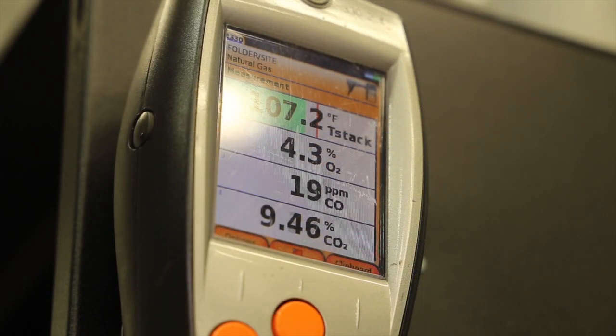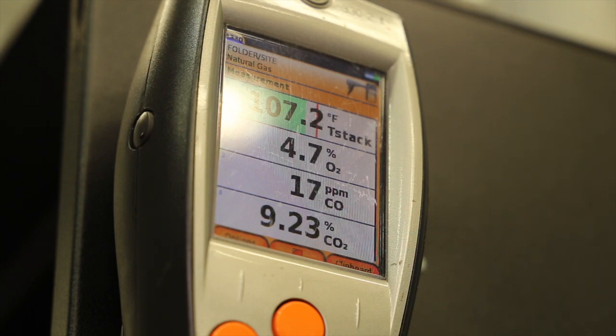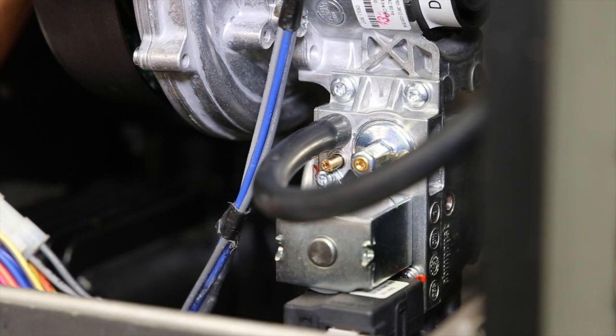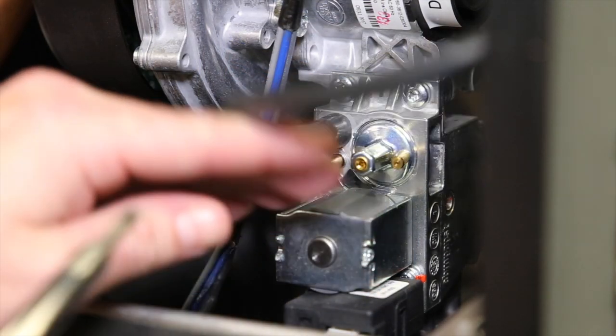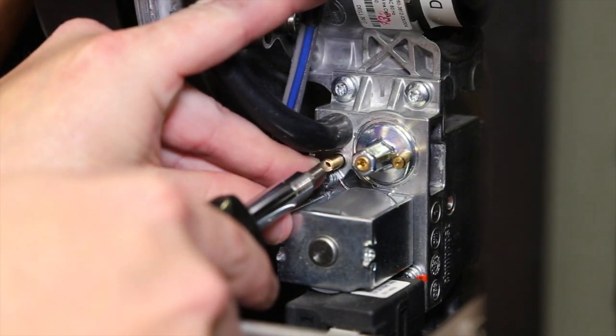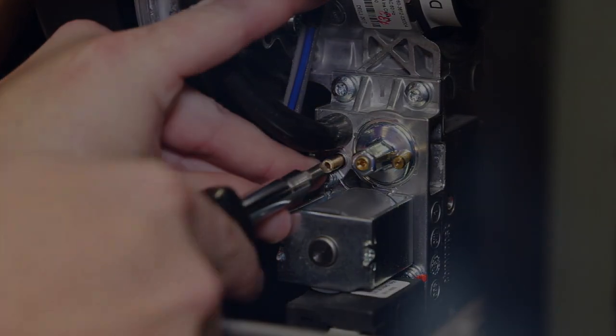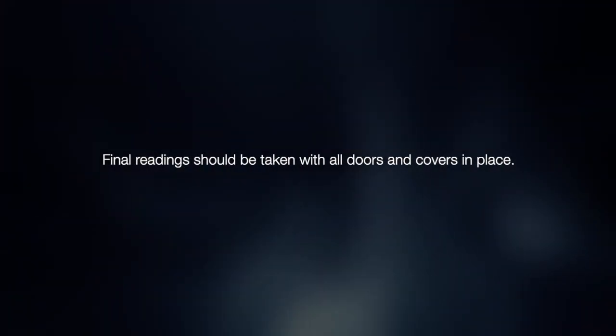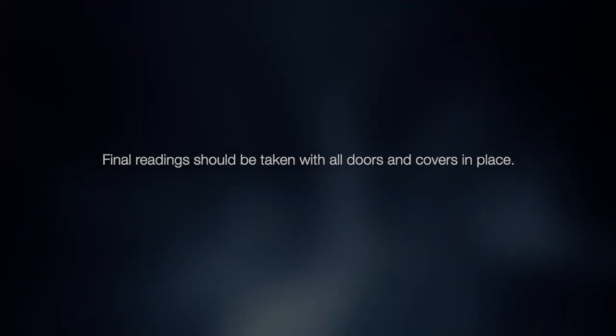After one adjustment of the gas valve throttle, allow the combustion to stabilize for at least one minute before rechecking the oxygen reading. If the level is still not within the specified range, repeat the adjustment procedure. Final readings should be taken with all doors and covers in place.